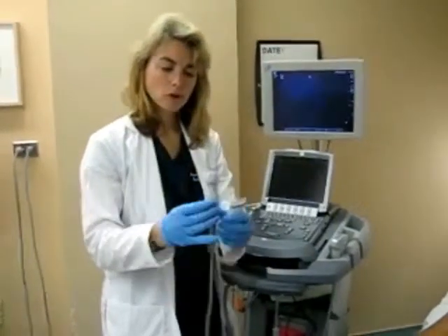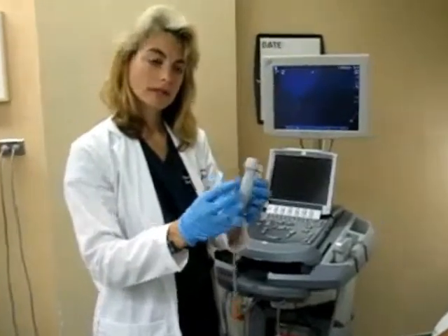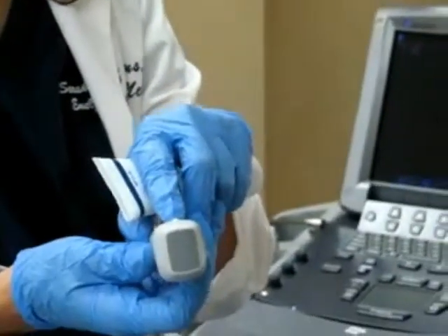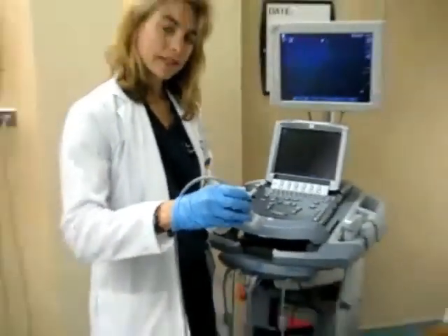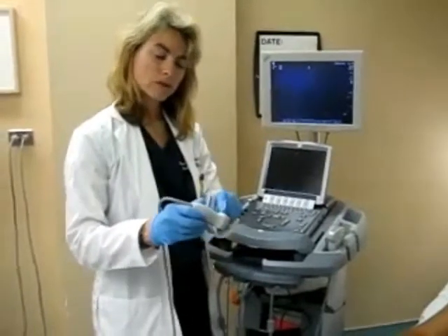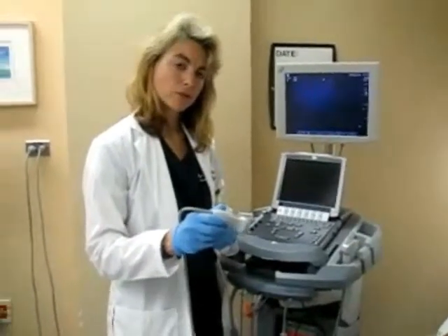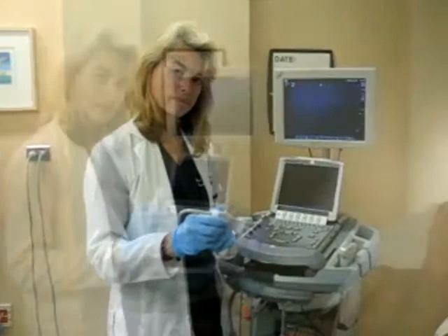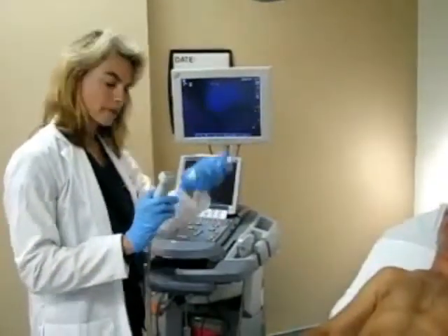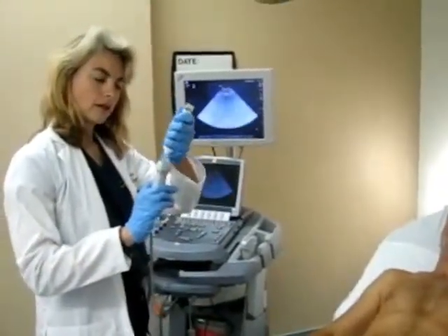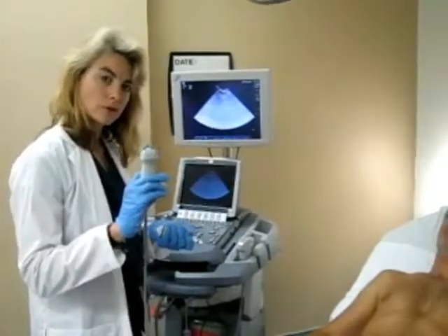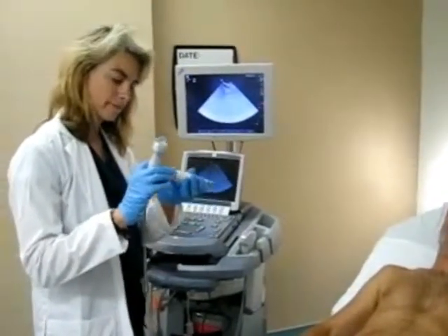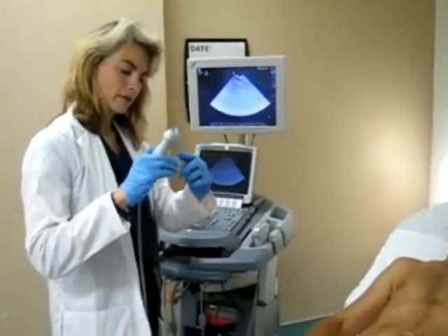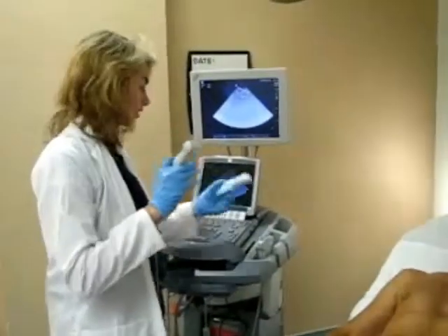You'll notice on the probe that there is a dot and a side without a dot. The dot, when doing the exam, needs to be either towards the patient's right side, if a transverse image is being obtained, or towards the patient's head, if a longitudinal image is being obtained. Place a copious amount of gel on the head of the transducer in order to allow the sound beam to transmit. Please replace the cap on the gel so that it doesn't leak all over the machine.